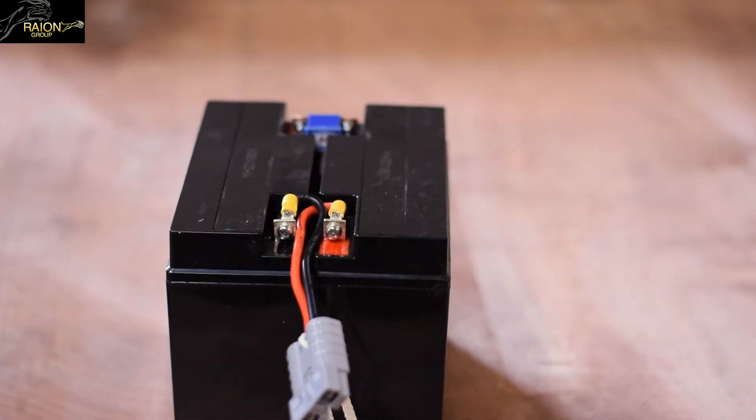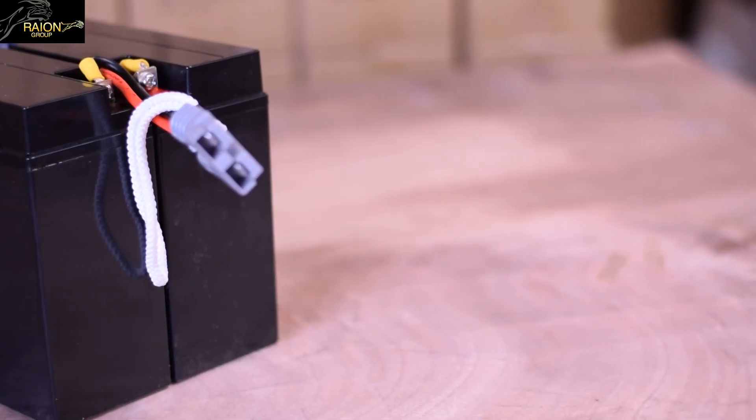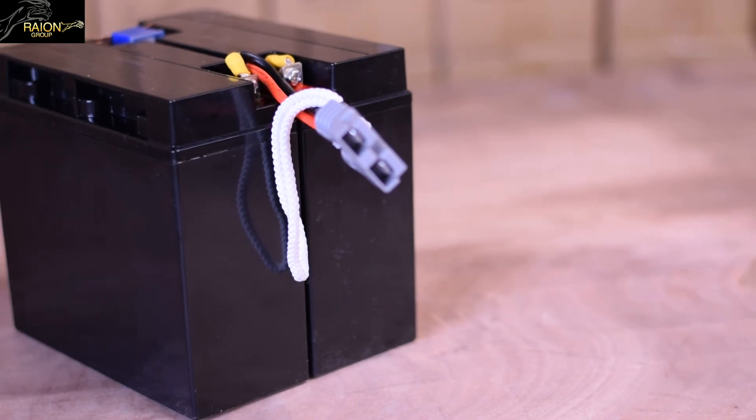Measure the cartridge voltage through the DC connector and it should read above 26V. Cover the terminal and fuse area with the plastic caps. Your RBC7 pack is ready for use now. The parts used and the full build kit are available in the link below.